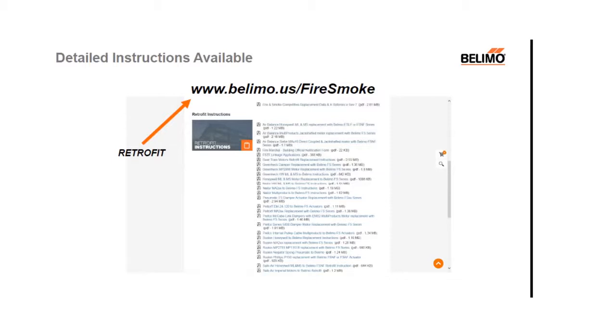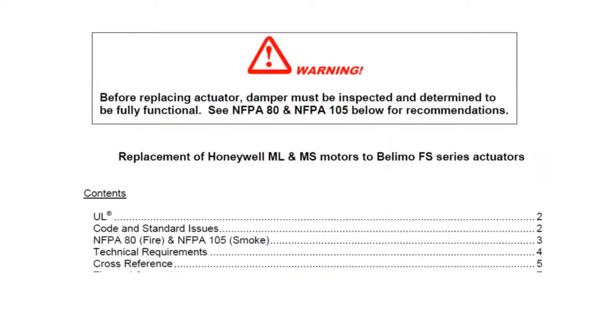Yeah, but you've got to know, a lot of the old dampers were two spring: one shaft spring with a fusible link. You leave those alone. Yep. Then if you've got an external spring, you've got to remove it. Otherwise, your motor would have to work against its own internal spring and an external spring, and that shortens the life of the motors. Yep. Couldn't agree more.